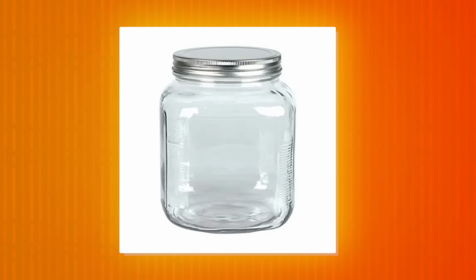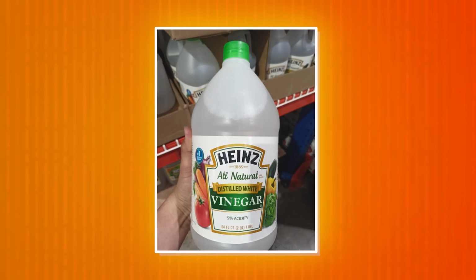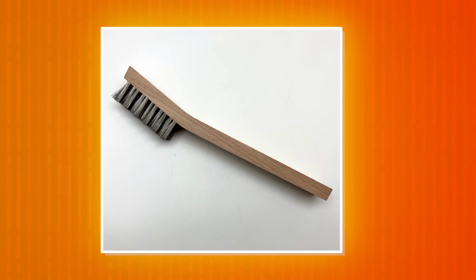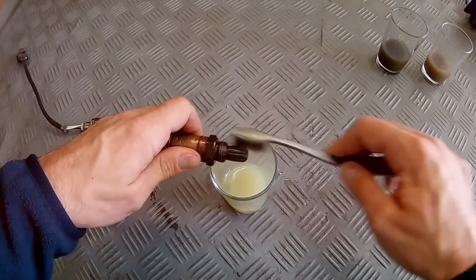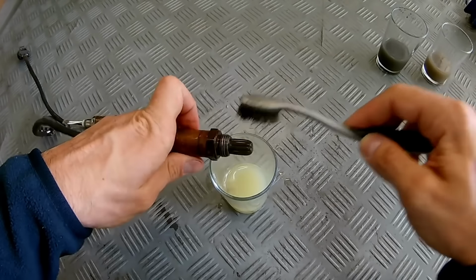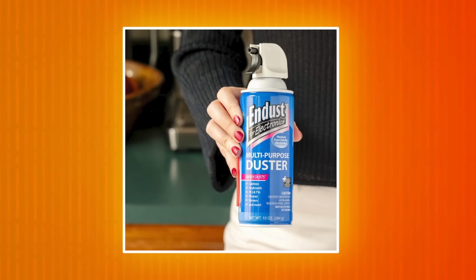A glass jar with a lid. Must be glass, not plastic. White vinegar. Genuine distilled white vinegar only. Baking soda. A small wire brush with brass bristles, not steel. Steel scratches the sensor housing. Compressed air. Anti-seize compound for reassembly.